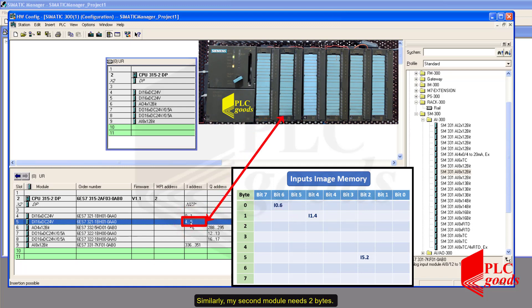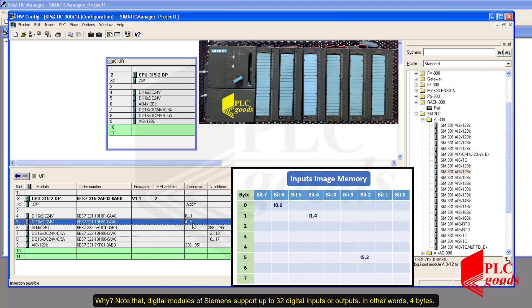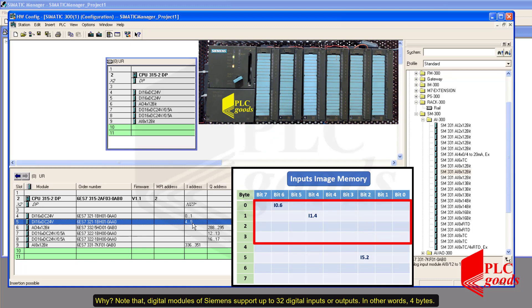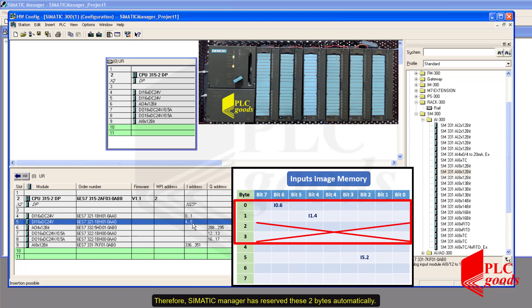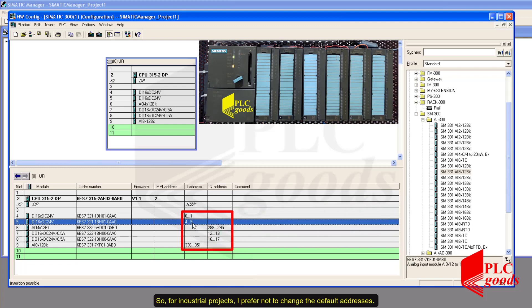Similarly, my second module needs two bytes. The PLC has skipped bytes 2 and 3 and then used bytes 4 and 5 for the second module. Why? Note that digital modules of Siemens support up to 32 digital inputs or outputs — in other words, four bytes. Therefore, Simatic Manager has reserved those two bytes automatically. Maybe I need to replace the first module with another one later which supports 32 inputs; in that case I can use those four bytes for the new module without changing the other addresses. So for industrial projects, I prefer not to change the default addresses.